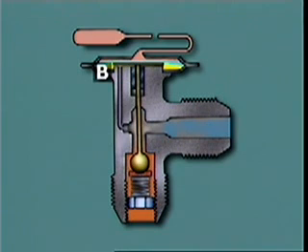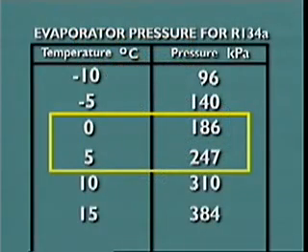The pressure in chamber B is determined by the refrigerant pressure in the evaporator and by the force supplied from the valve spring, often called a superheat spring. The spring is designed to ensure that the temperature of the refrigerant leaving the evaporator is between 2°C to 9°C higher than the boiling point of the refrigerant at the current operating pressure.